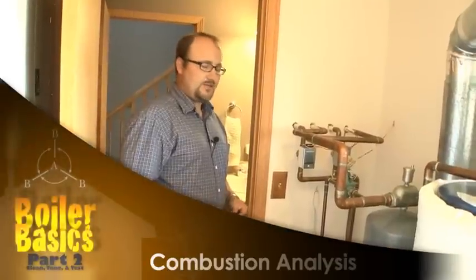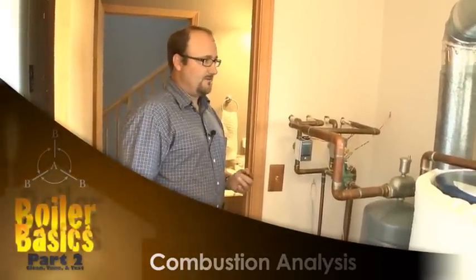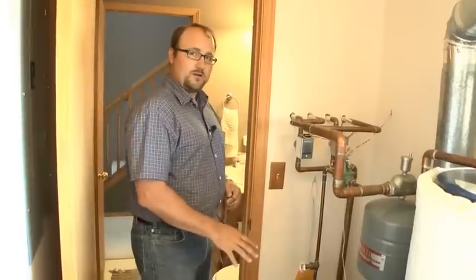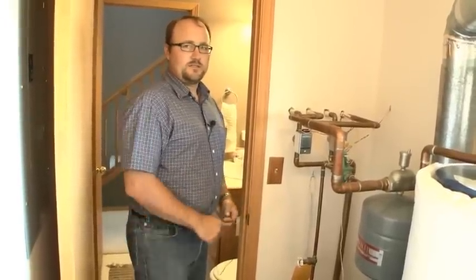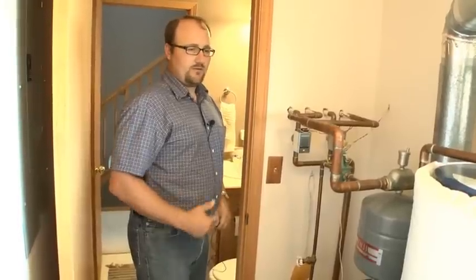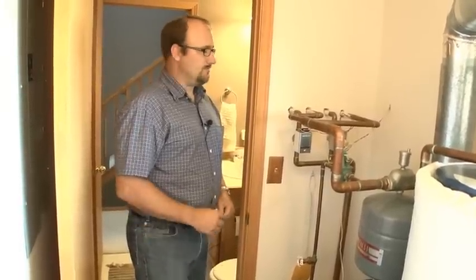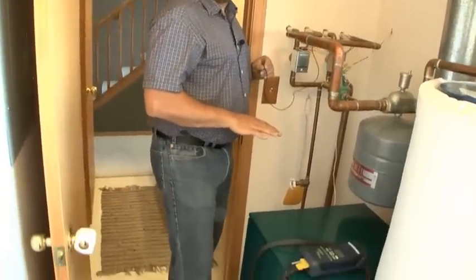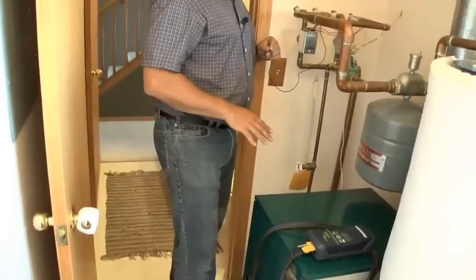Okay, at this time we're going to check combustion efficiency of the boiler. Really what we're looking for is carbon monoxide. We're looking to see if this thing has a good burn, if it's getting the right amount of fuel, right amount of oxygen. This is a cast iron boiler. We don't want this boiler to run too efficient. It's not designed for condensing.